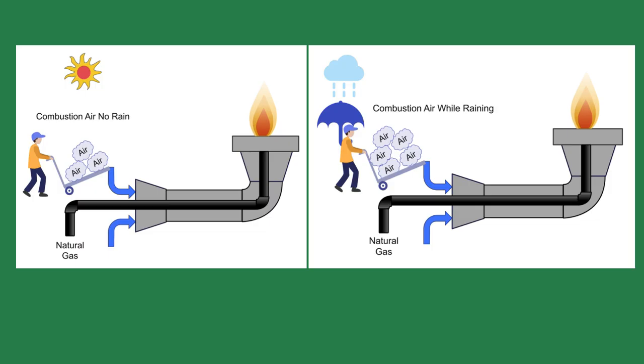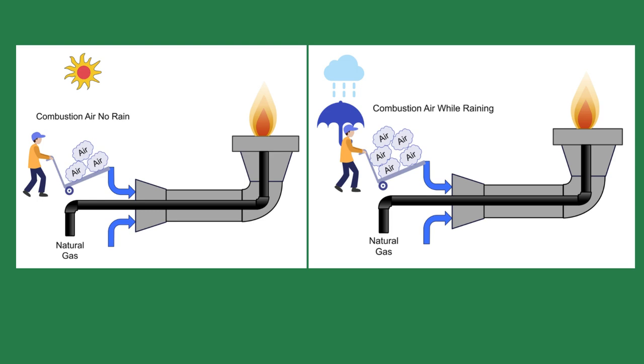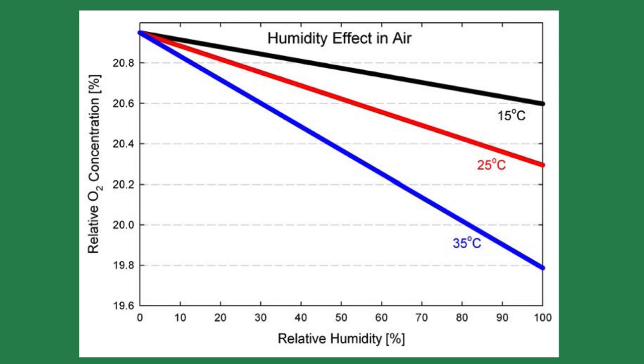The other factor affecting the air to fuel ratio when using combustion air vented from outside is humidity. Moisture displaces oxygen in the air, so you need more air when it's raining than when it's dry. At zero percent humidity, the oxygen level in the air is about 20.9 percent. At 50 percent humidity, the oxygen level drops to 20.5 percent. At 100 percent humidity, it drops to 20.1 percent. Combining rising humidity and rising temperatures can create a bad situation.